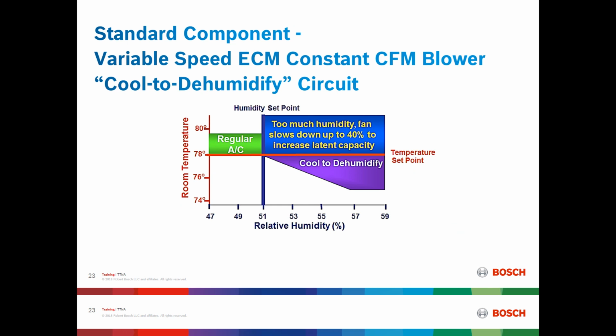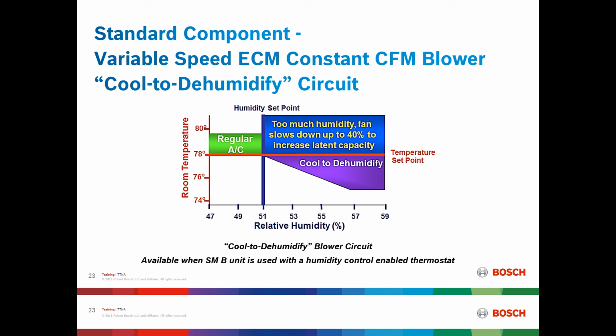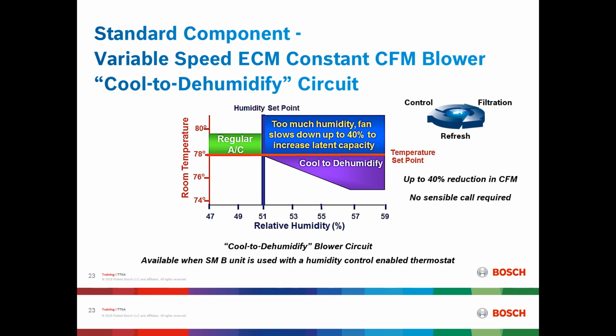This particular blower has a cool to dehumidify circuit built into it. What this means is that available with the SMB, if this particular unit is coupled with a thermostat that has humidity-enabled control, and the relative humidity is above a preset value, but the sensible load is met, the unit will actually stop the call from the sensible call, but continue to run and dehumidify and cooling with up to a 40% reduction in CFM with no sensible call required. This helps in dehumidifying the air.